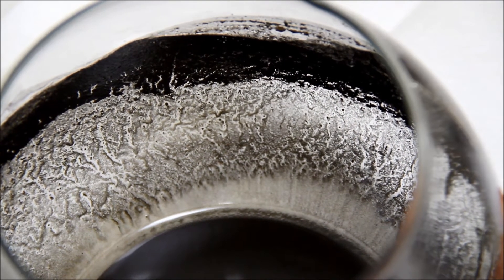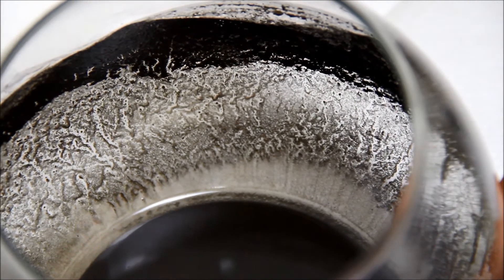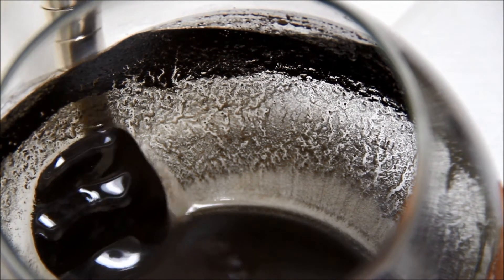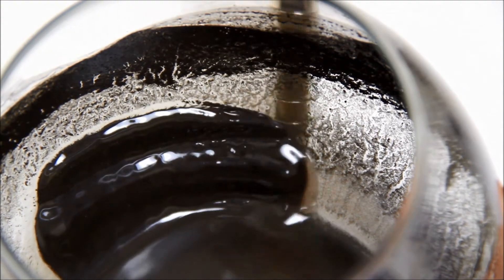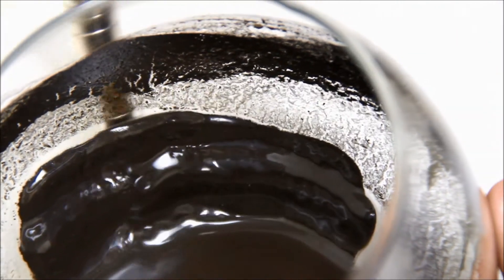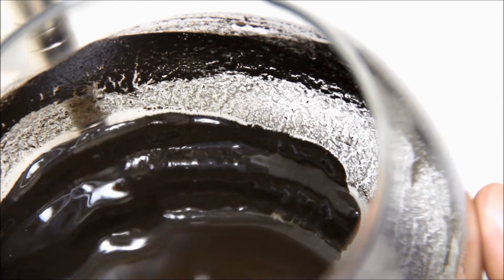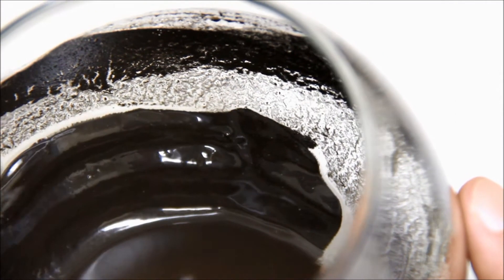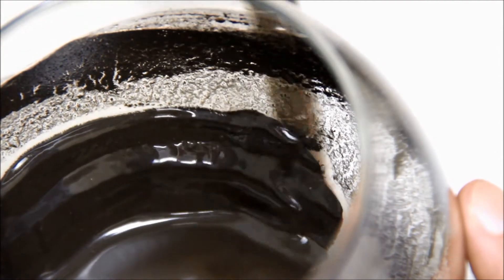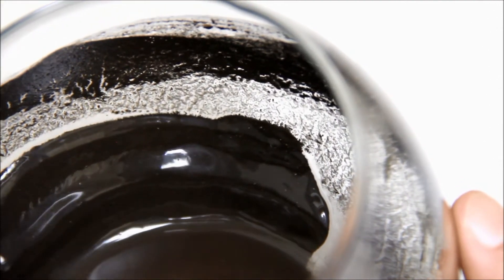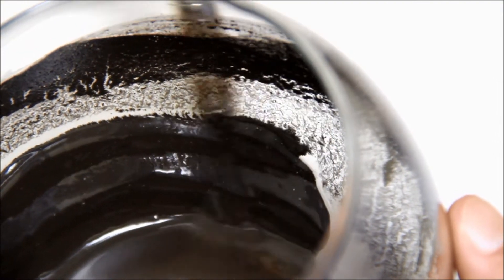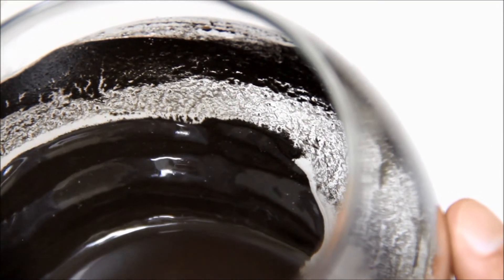So I just want to show you what was found inside that filter. As I bring the magnet here from our TF1 and drag it along the sides you can see the rust and magnetite attract to the magnet. And it's actually pretty thick stuff there on the side of the wall. So this is what was inside of your heat exchanger, of your boilers, your pump seals, and over time can really break down the components of a heating system.